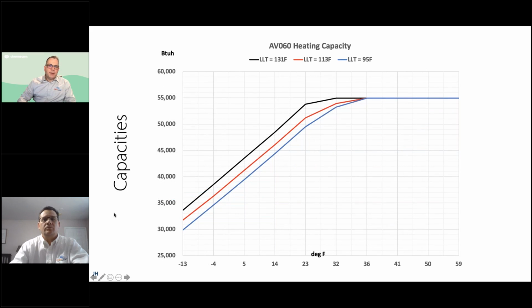Capacities are equally impressive. We take advantage of that vapor injection and variable speed scroll. So you can see the maximum capacity of this 5-ton unit. There's also a 2.5-ton unit, is about 55,000 BTUs per hour. As it gets colder outside, you can see even at the minimum temperature, we still have more than half the capacity. That's pretty unusual for an air-to-air heat pump. We typically are significantly less capacity, even at 0 degrees outside.